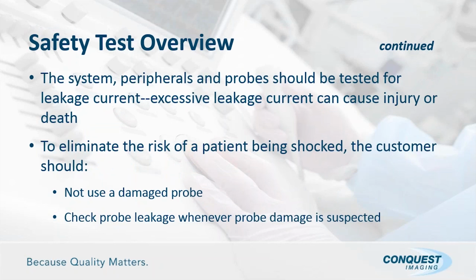The system, peripherals, and probes should be tested for leakage current. Excessive leakage current can cause injury or death. Well, there's a couple things in this that I find interesting. We have to say excessive leakage can cause injury or death. When we're doing an ultrasound, there's a high potential that the patient is already somewhat stressed. Say they have a pacemaker, so they're under conditions that may have already weakened them. So even though the leakage that we're talking about may seem unsafe or not unsafe, in reality we have to be very aware of it.